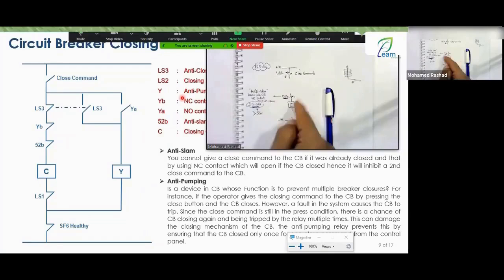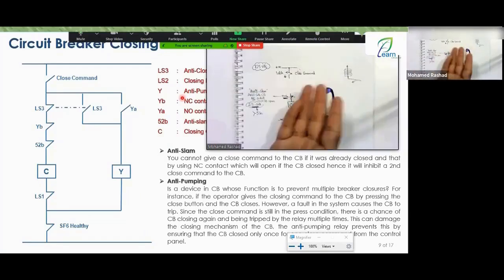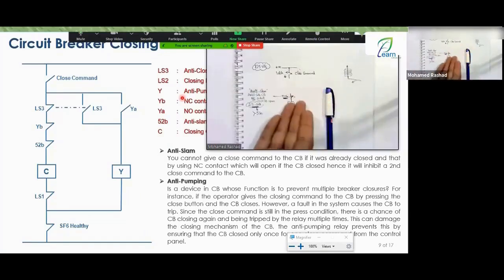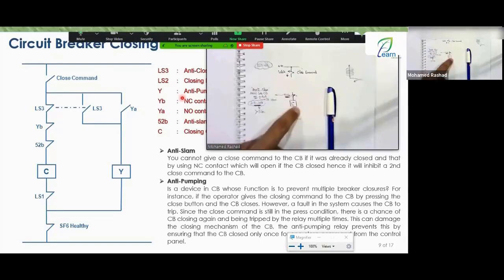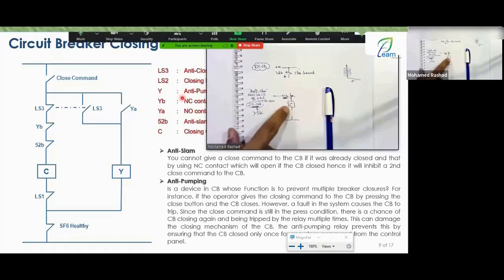Now the breaker closed because the fault that caused the breaker to trip is still present, because you haven't fixed anything yet. The breaker just opened and closed again, and then the breaker will open again. What happens next? It returns once more. It finds the fault present, right? So it closes the breaker again. So the breaker keeps closing and opening. It finds the fault, so it closes and keeps operating in this manner.